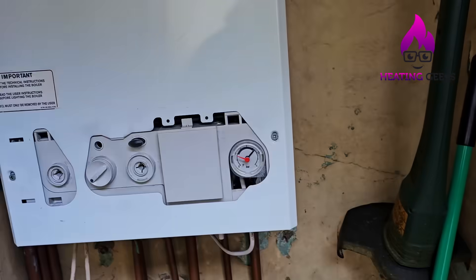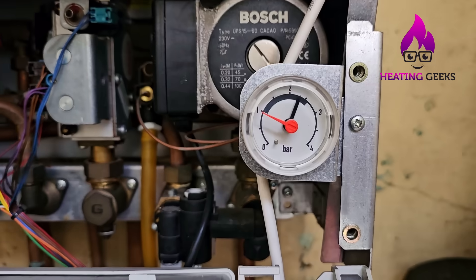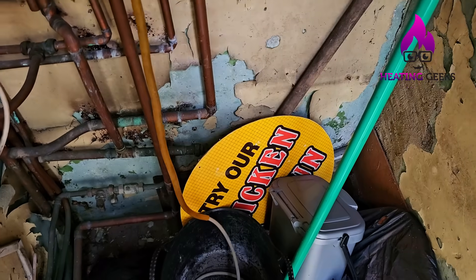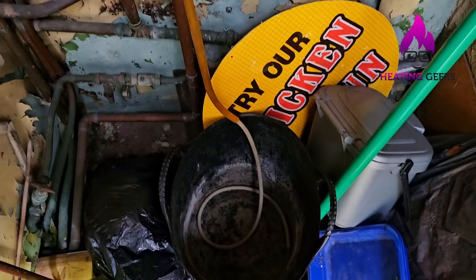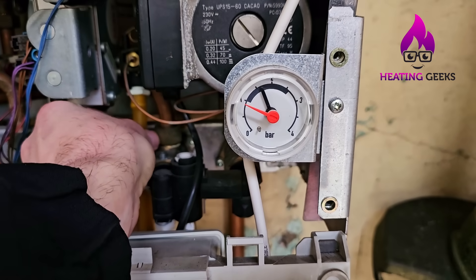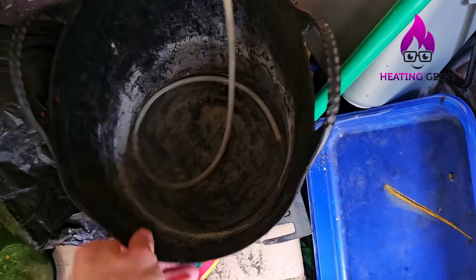So when I drain this boiler I reckon I'll have two to three inches of water — maybe even less — and that'll be all that water in the bucket. Let's get set up: take this off, undo those two screws, get access into the boiler, take this cover off. The boiler's turned off, power's off, and pressure is slowly coming down as it cools. Look how quickly the pressure's dropping and look how much water's in the bucket right now.